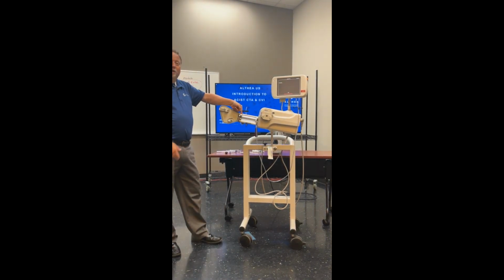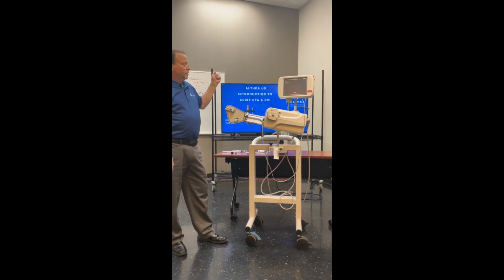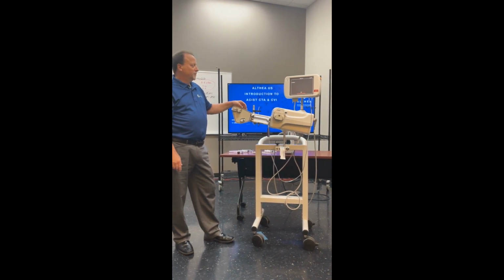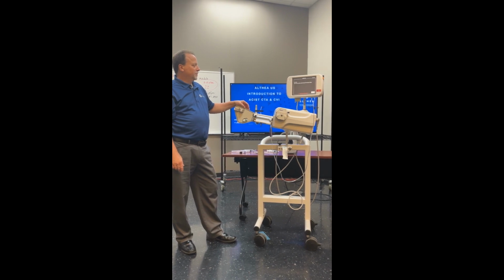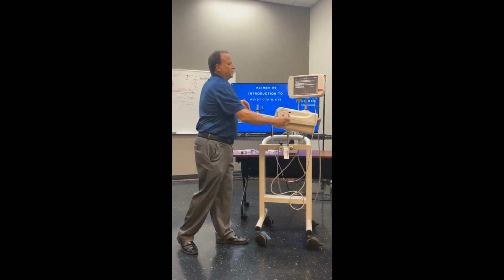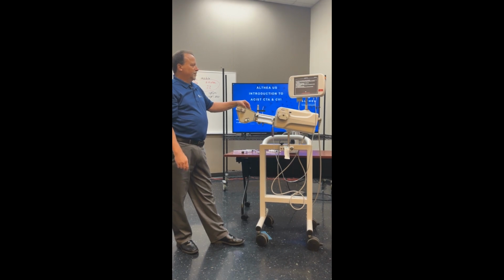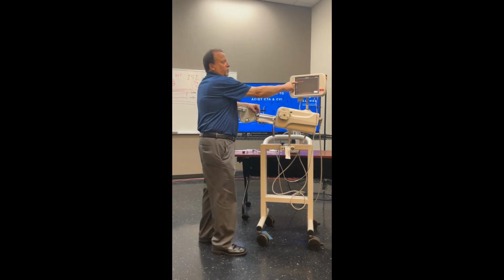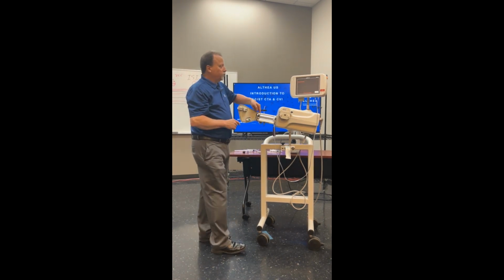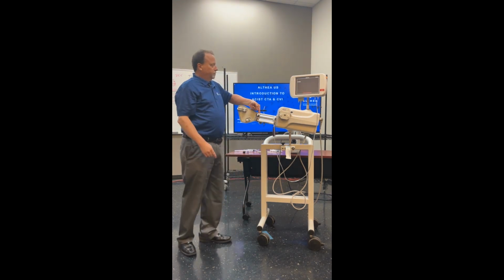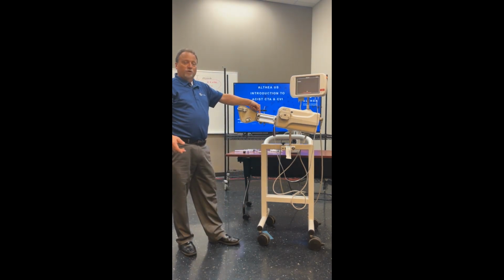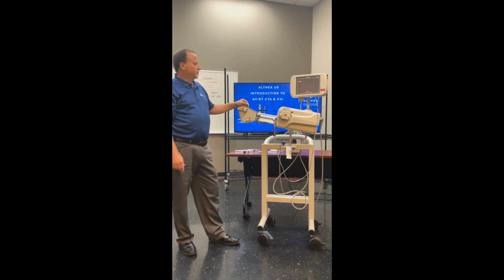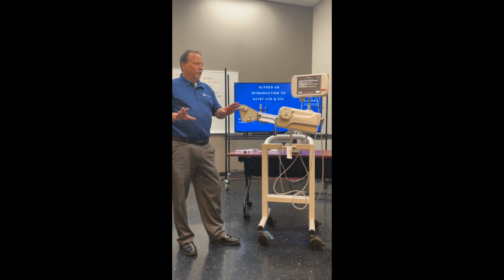Now it's going to purge. I'm going to let it go for about 2 or 3 seconds. Release my finger. It's going to go filling again. So it's going to go through purge and fill several times, and each time it says syringe valve closed, you will use your finger to simulate it. Let it purge for 2 or 3 seconds. Release your finger. Now it's happy. It's purged a couple times.